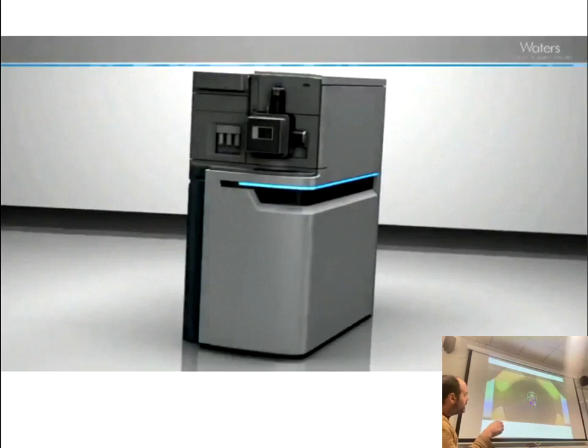And then what happens is, here is the collision cell, you can imagine. They're not showing here that there are gas molecules, but the idea is that the red one is now colliding with these gas molecules, and it's breaking down into smaller fragments. So bits of it are coming off, yeah? So you've got fragments, but you can still have the precursor, because we'll come to that. Now you've got all these fragments, and you put them through the ion guide, and this is a time of flight.